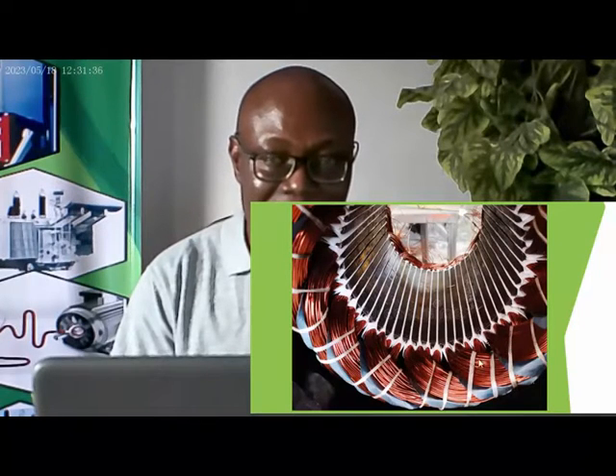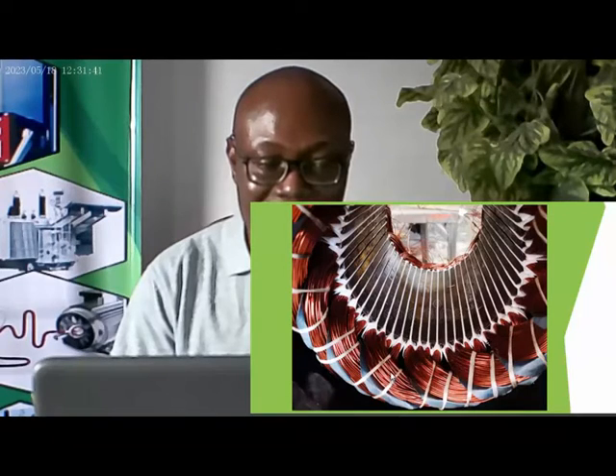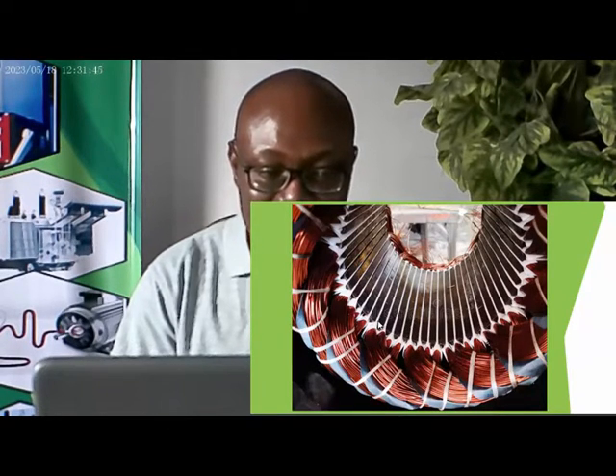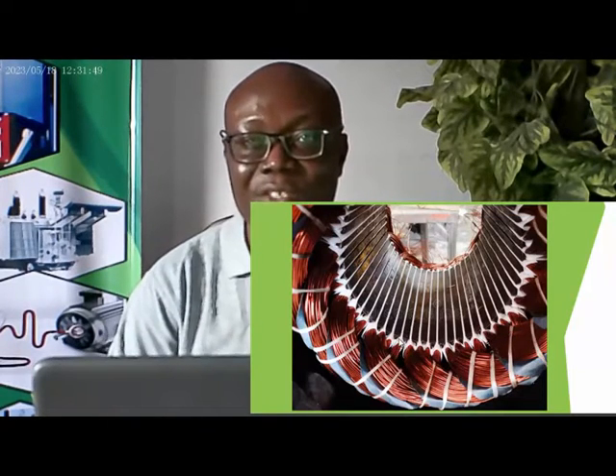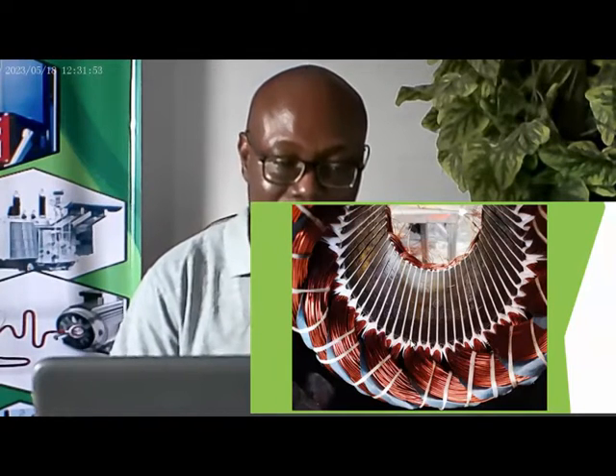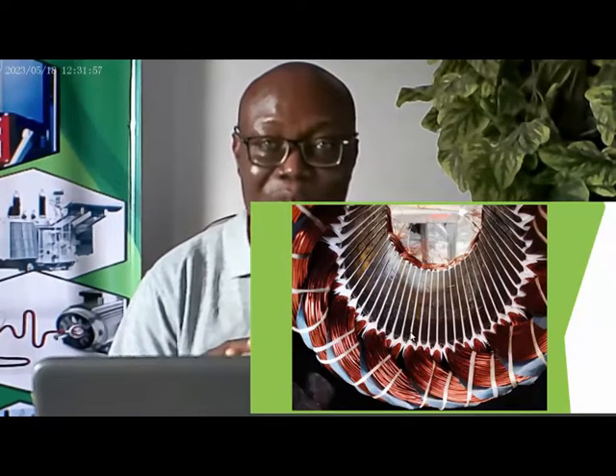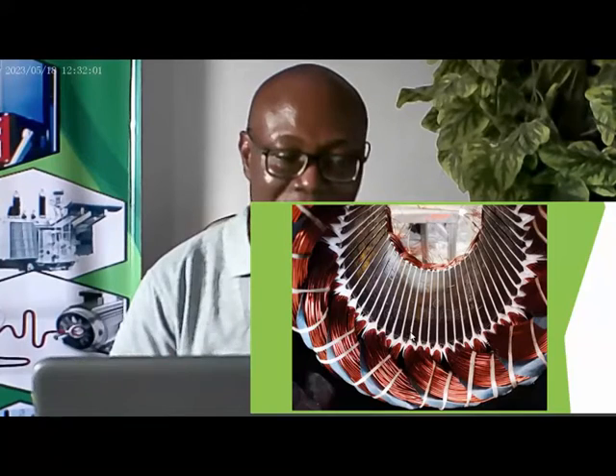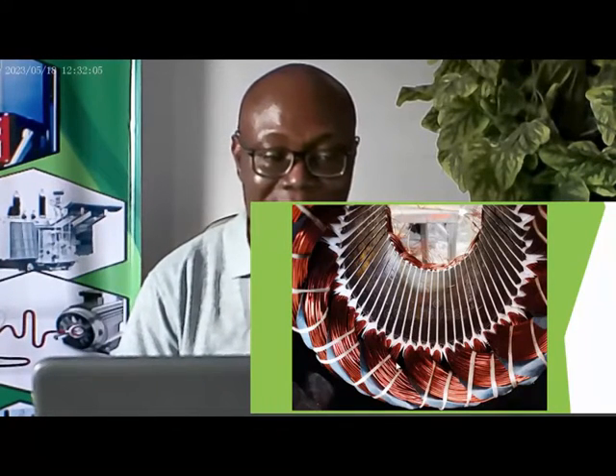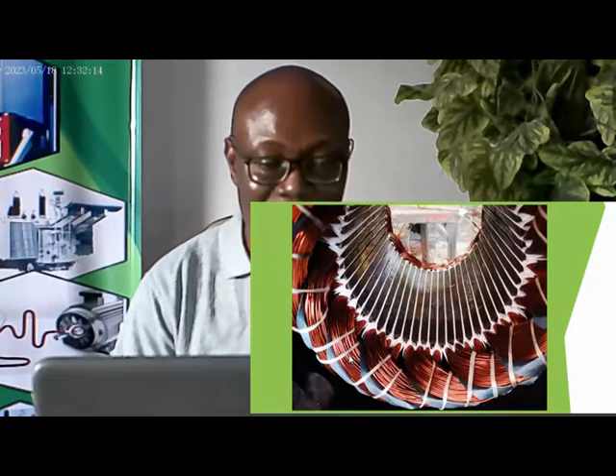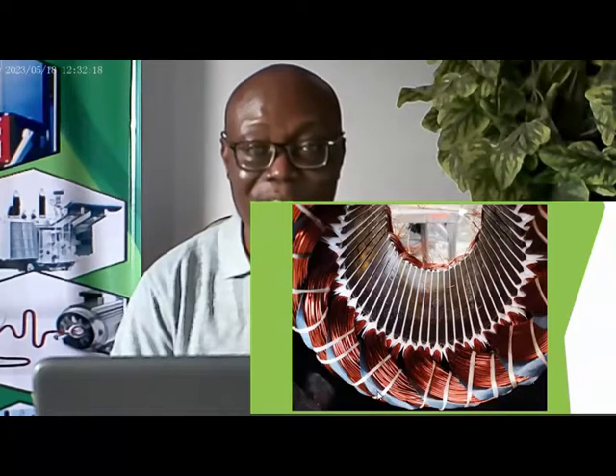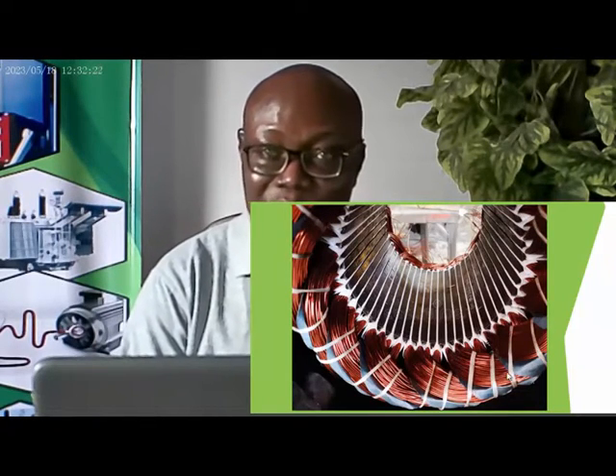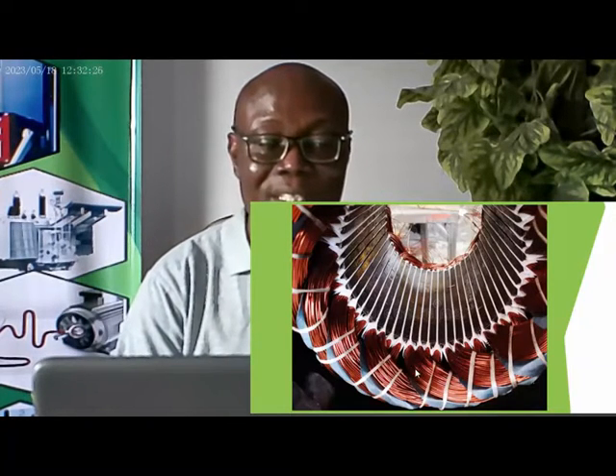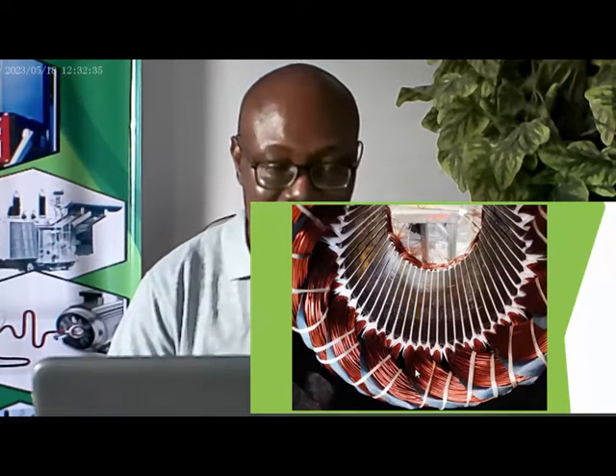So when you are testing any of the phases to ground, what you are testing is this insulation, this separation between the winding and ground, to see if it is still strong enough to withstand the voltage pressure that will be applied to it. Then when you test between lines or between phases, line 1 and line 2, or between U and V, or between U and W, what you are testing is the insulation of the materials used to separate each of the phases. Since they don't have any interaction with each other, you do not expect the insulation resistance to be low. You expect it to be high, depending on the kind of insulating material that is used.